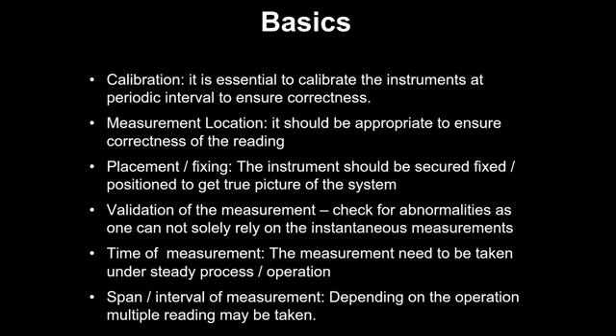So we thought maybe we are wrong. We started talking with their process people, but they agreed with us. They said, yes, there may be a problem, because 6 months back we were running only one compressor. Now we have to operate two compressors for the same load, because nothing has changed. So either the leakages have increased or the compressor capacity has gone down. Because this problem was validated by the plant people beforehand, they called the service engineer for the compressors. The service engineer came, checked the compressor, opened it, and saw that some non-return valves had got damaged. So the non-return valve was not functioning. The piston was just moving backward and forward, but the air was not getting delivered. That was the reason. They rectified it, the saving was validated, and they got the saving. But we always try to check, because a sudden 50% capacity compressor means there can be some other issue also.